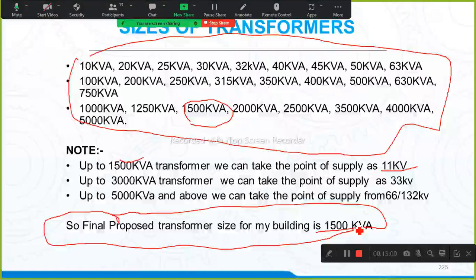Now 1500 kVA means what should be the point of supply? 11 kV should be the point of supply, because for transformer sizes up to 1500 kVA, we need to take the supply from 11 kV point of supply as primary. Okay, secondary, we are stepping it down to 415 or 3.3 or 6.6 based upon your requirement. But secondary we are reducing to 415 volts for my building. So now I got the transformer size as 1500 kVA.